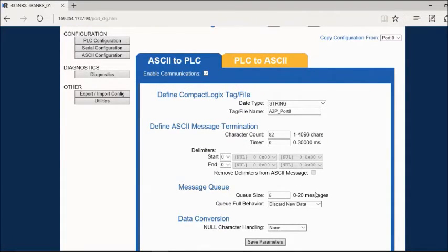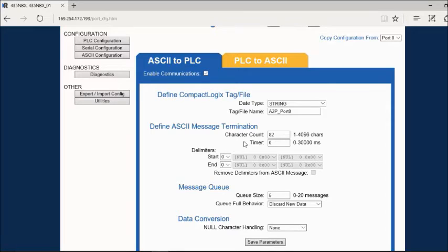Next you see the defined ASCII message termination. One of these three end cases must be met for our gateway to consider a message complete and send it to the PLC. The first is a character count, which defines how big your message could be. The second is a timer — this is the maximum amount of time the gateway will wait between receiving ASCII characters. Once this timer expires, the gateway will send the message.